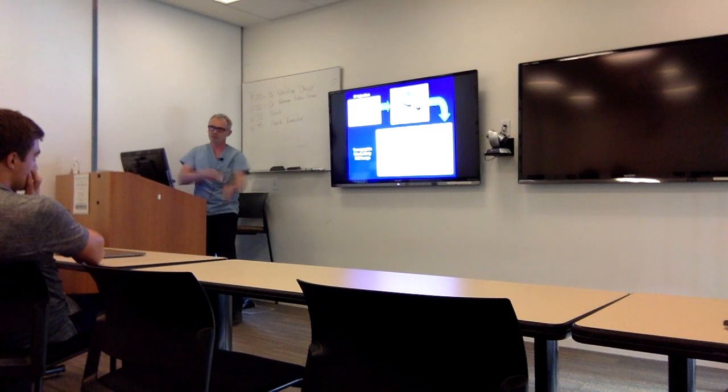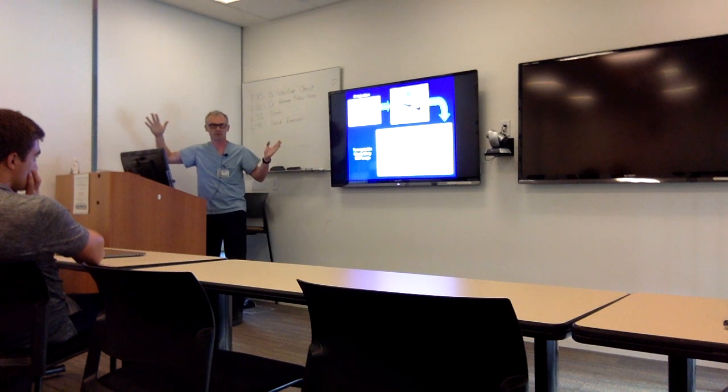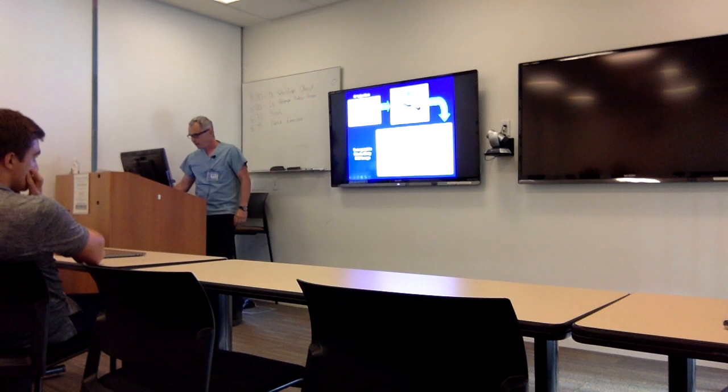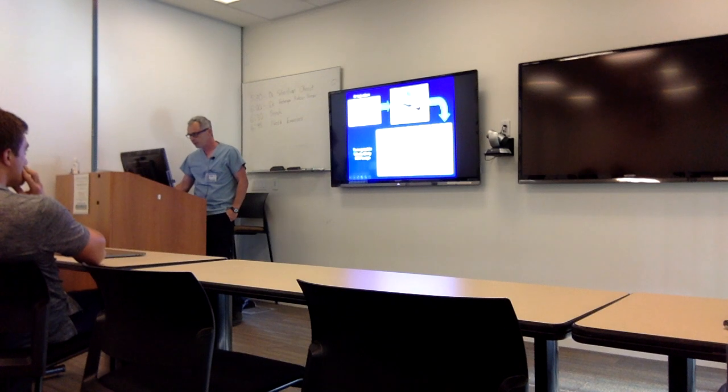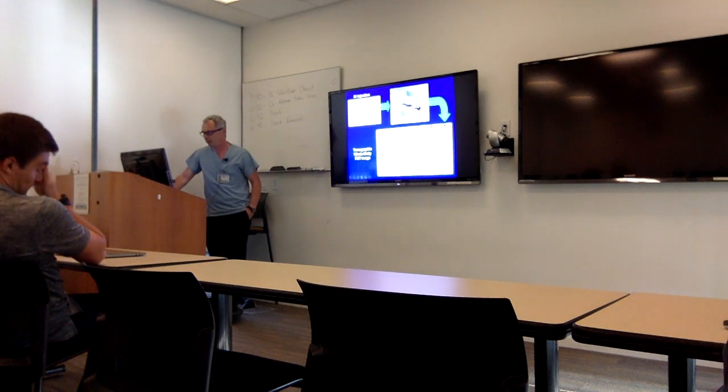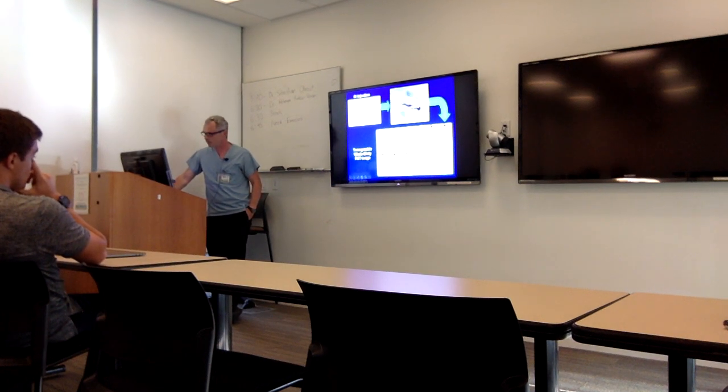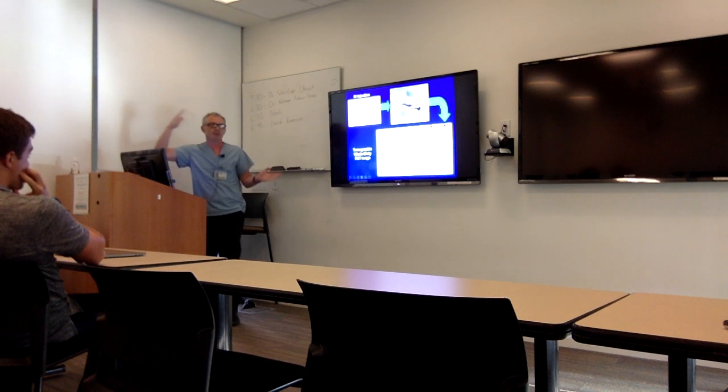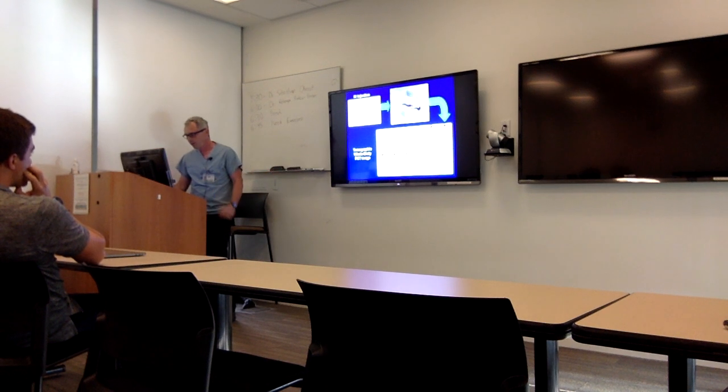This is where you inject the tracer, and it's radiating out. You can see a patient under the camera here in this picture, and these are detectors all around. You can see there was an event that took place right here, where 1 gamma ray went one way and 1 went the other. Because these 2 detectors detected a gamma ray simultaneously, we figure it probably started someplace along this line.